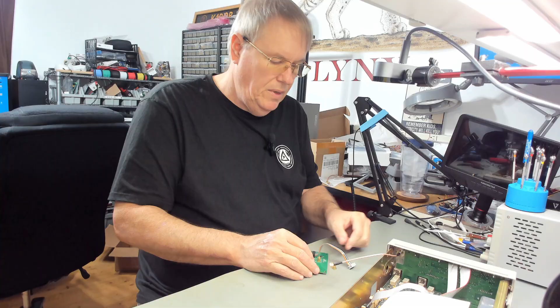Step one, let's put the spacers on this board and see if we can get it in there. This plug's got to go in like that. So we're going to install our spacers. All this board is, while I'm doing this, is nothing more than an amplifier or a set of low noise amplifiers into a divider chip. It takes the signal in and amplifies it up, and then feeds it into a dividing chip set for like 64 or 128 or whatever it is. Your pulses coming in from your frequency source get divided down by a certain count, which then feeds into your 225 megahertz counter.